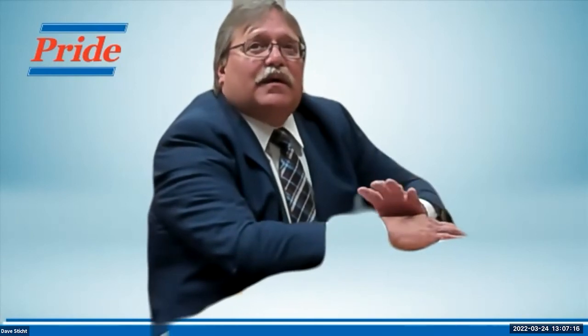But I would highly recommend, if you have Division 1 and Division 2 areas, to keep the mindset of the personnel always keyed to Division 1. Yeah, I read that too. And also what I've seen, what's happened in the past at some facilities, is that because their mindset is built around how do we make things Div 2 or less, so it's cheaper, they end up cutting corners and really kind of fooling themselves.